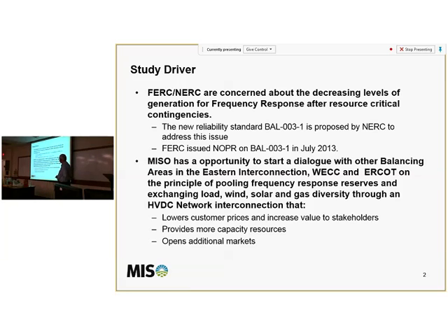And with the markets coming up, people aren't paid for that anymore. And if they're not paid for it, they don't do it, because it costs money to have extra pressure and extra temperature. There's heat loss, and then you get valve losses when you open the valve. So the boilers are now being run, a lot of them, on what's called once through. They balance the input to the system to the output of the system. There's no reserve, and therefore the margins are coming down to what's required instead of what was. People get all upset about that because they think it's a decline, but they gave them market signals to do that. They did it, and now they're upset about it. So that's politics.